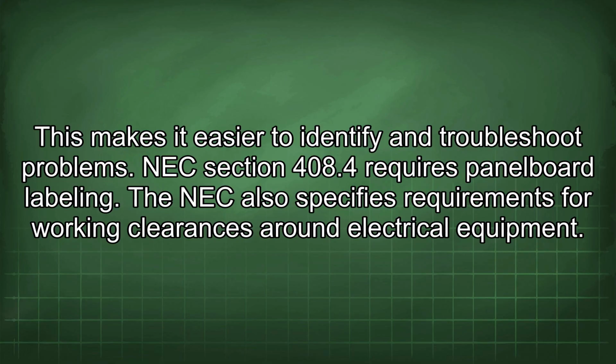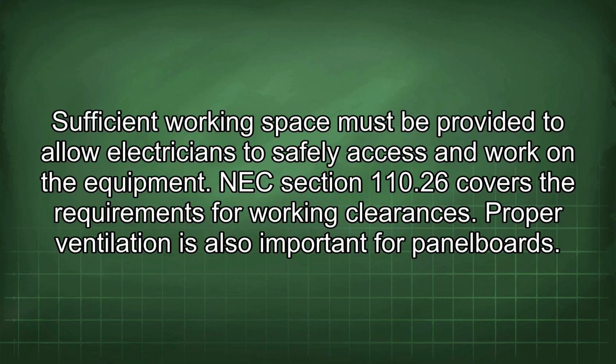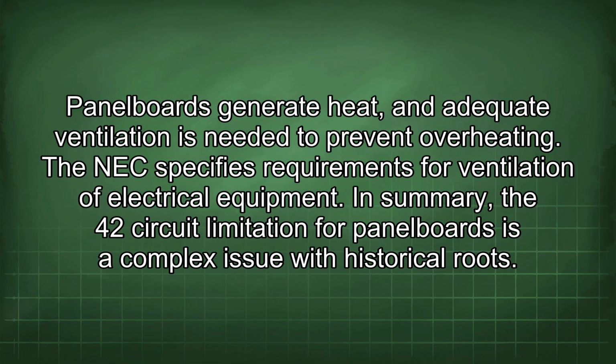The NEC also specifies requirements for working clearances around electrical equipment. Sufficient working space must be provided to allow electricians to safely access and work on the equipment. NEC Section 110.26 covers the requirements for working clearances. Proper ventilation is also important for panelboards. Panelboards generate heat, and adequate ventilation is needed to prevent overheating. The NEC specifies requirements for ventilation of electrical equipment.